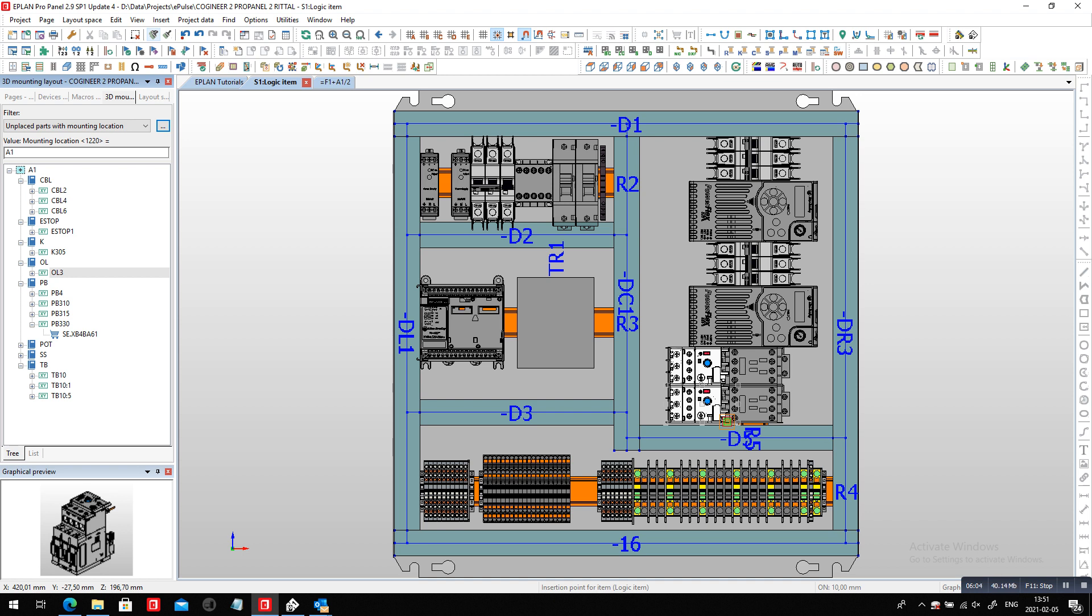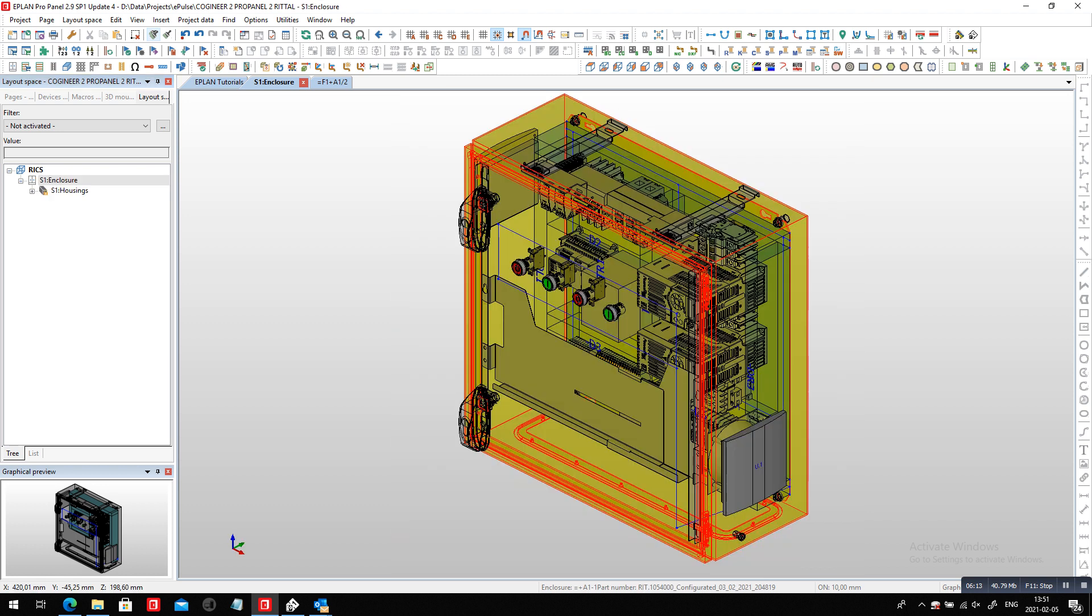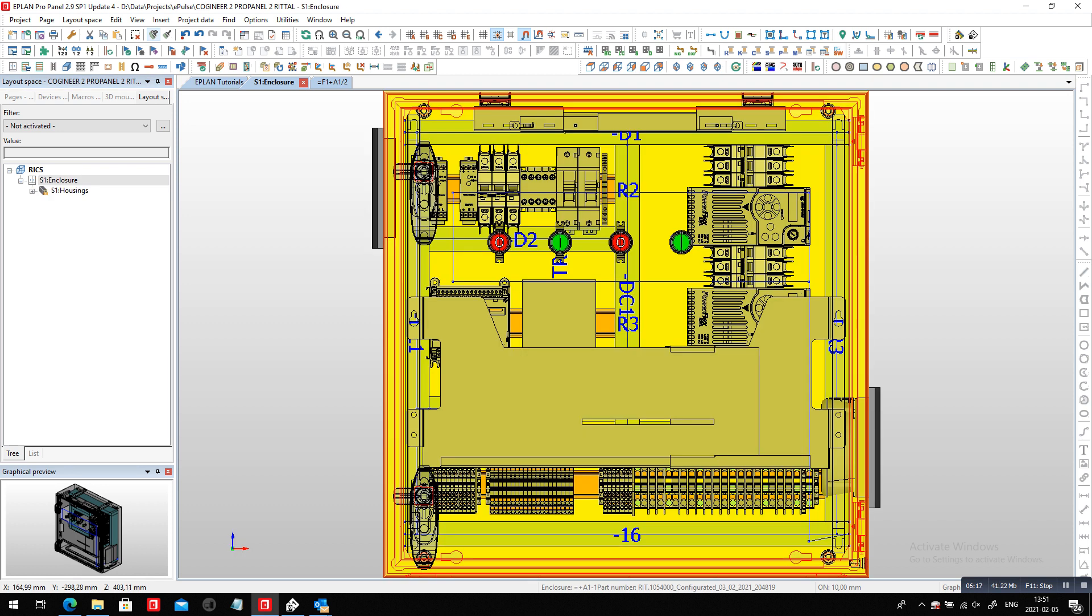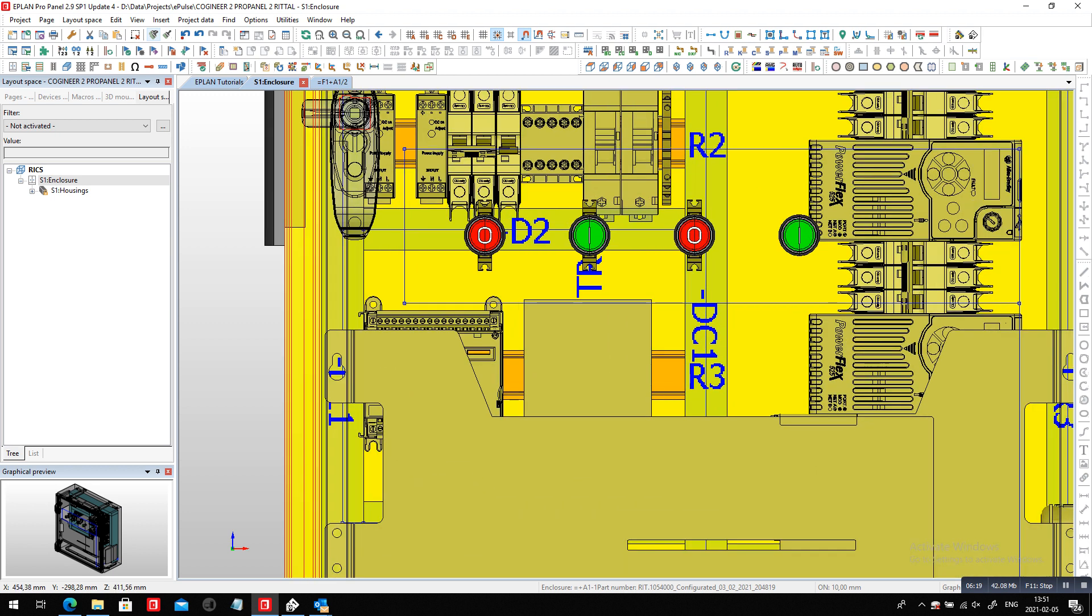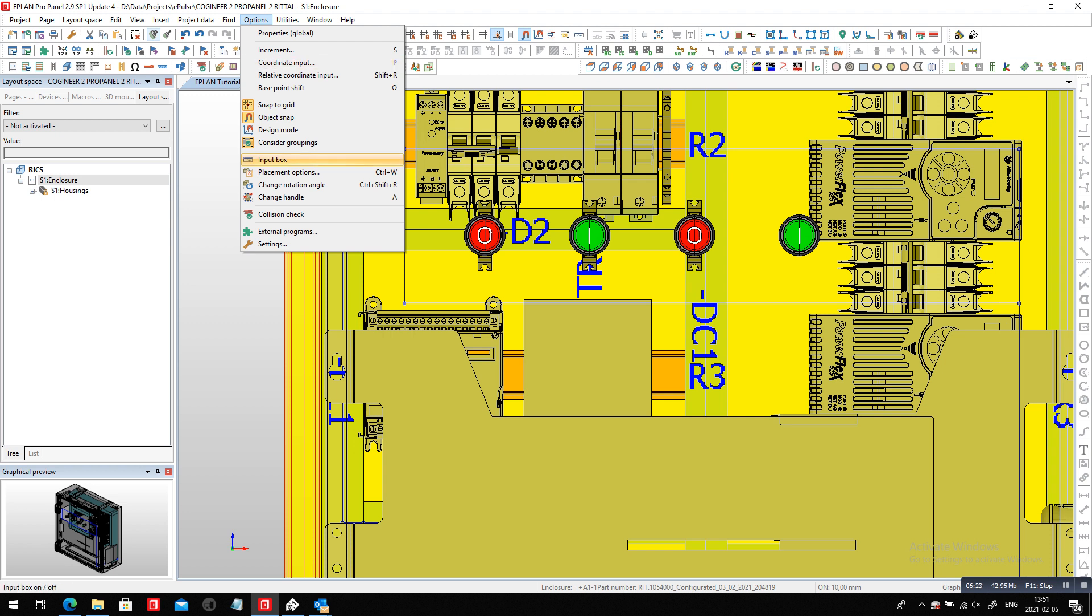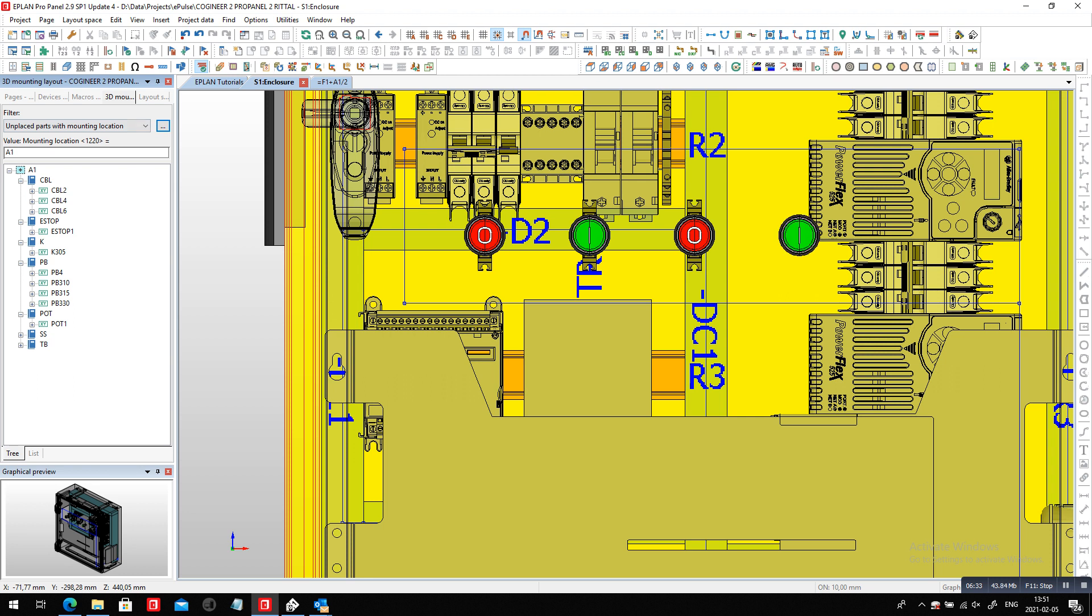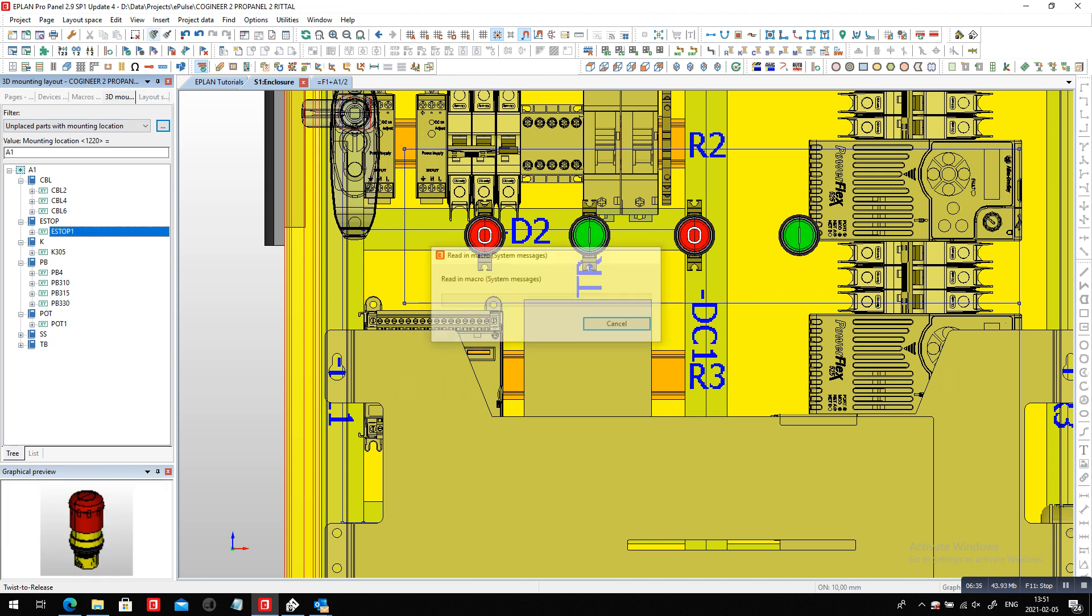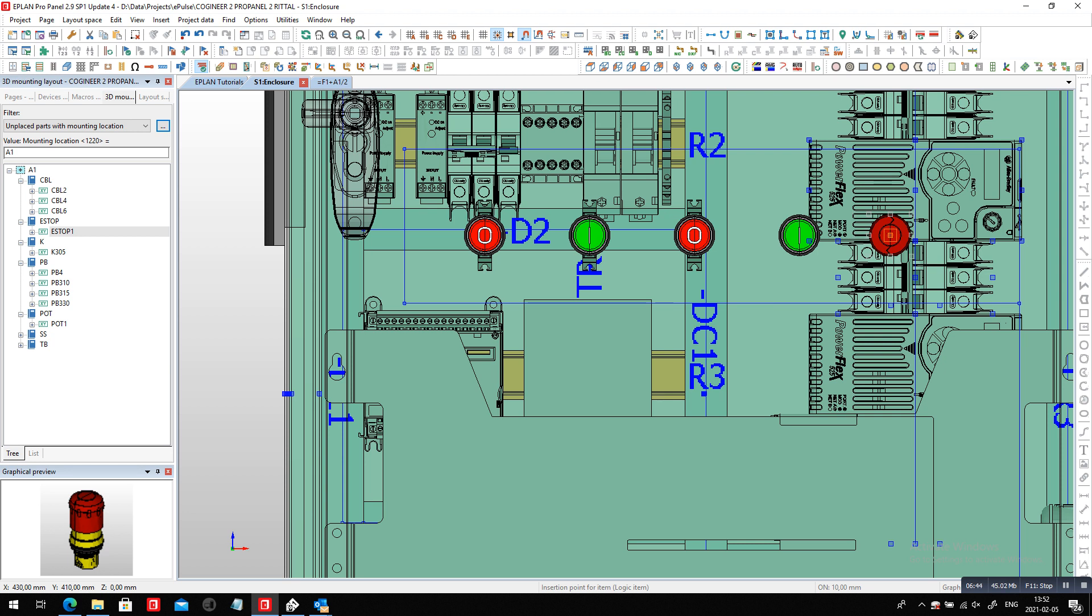A couple of push buttons and other items that actually shall go on the door. So let's finish this up here and open the door. Door is actually directly to be accessible like this. Now, I do have a couple of items already. When I do place the door, I like to turn on the collision check because very often the collision check will prevent my push buttons or items that I place to collide with anything that's in the back. So let's say here, this bigger push button, if I try to place it here, we'll see if it actually fits. If it fits, I can actually place it. If it doesn't fit and it actually warns me, I should then just be careful because it would probably collide with the object in the back. If it doesn't, then we're happy. We're good. We can place it.